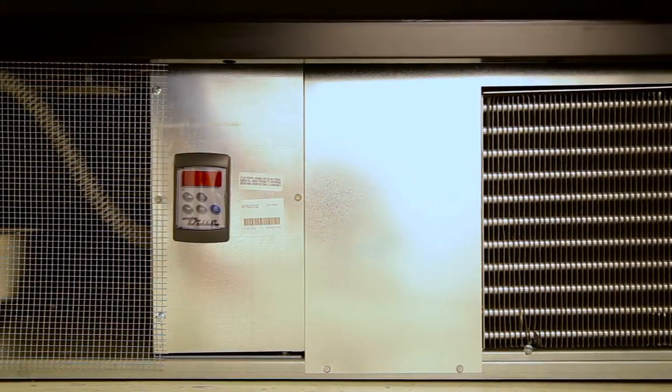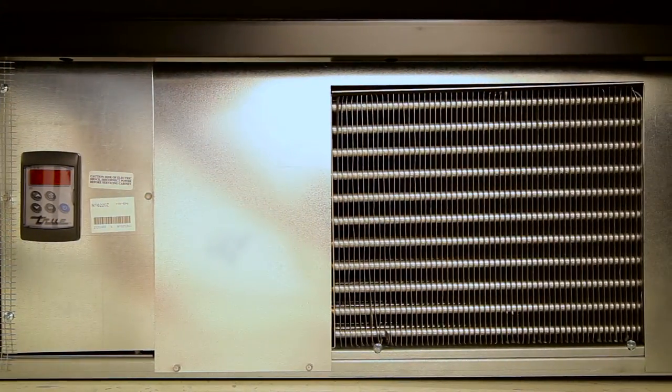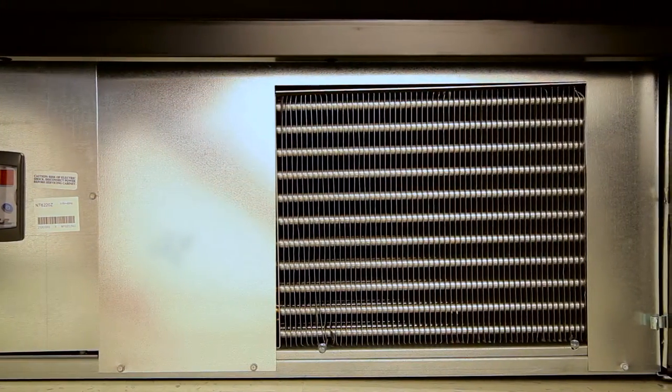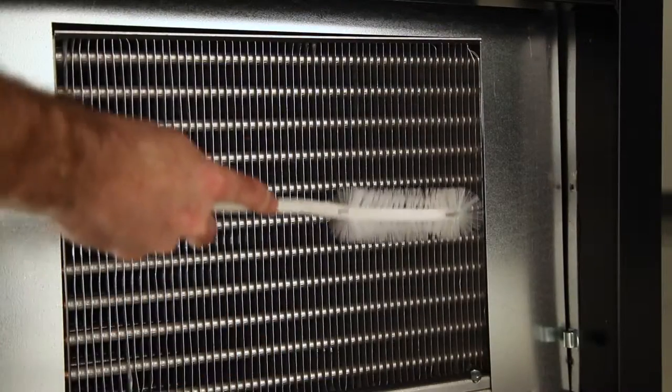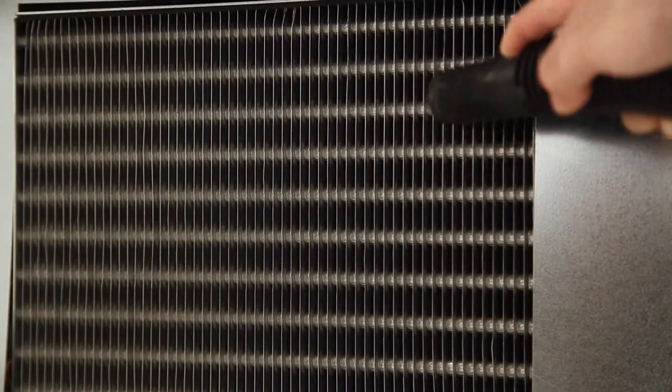A recommended rule is to check the coil every month for the first three months of use. This will tell you how dirty your environment is. Generally, you should be cleaning the condenser coil every 60 to 90 days, depending on the environment in which it is used.